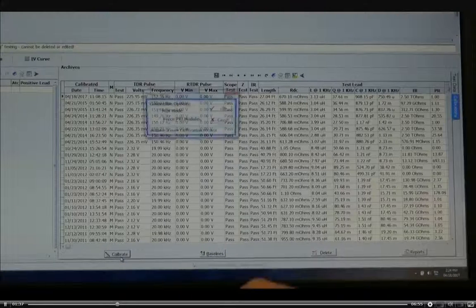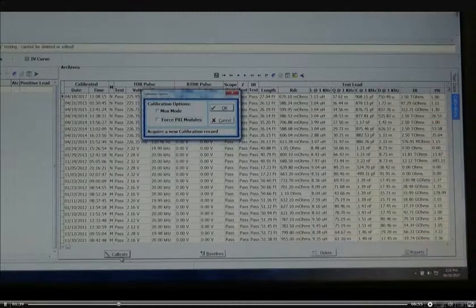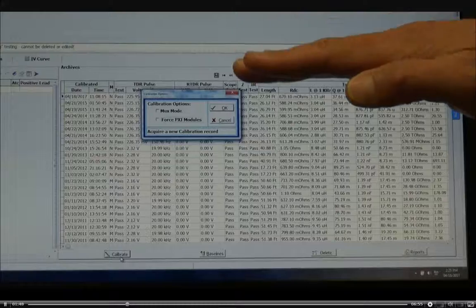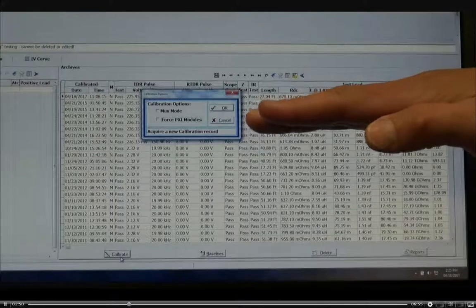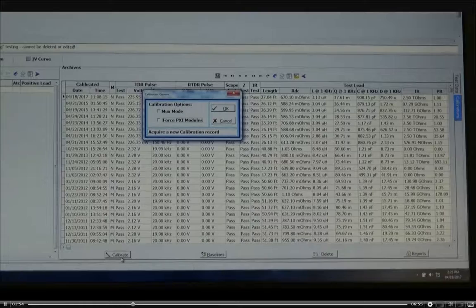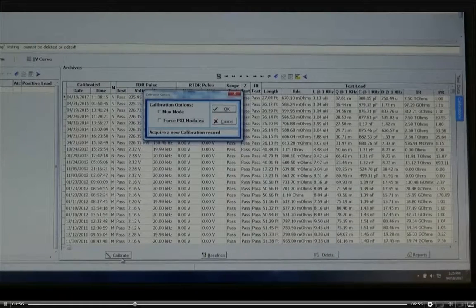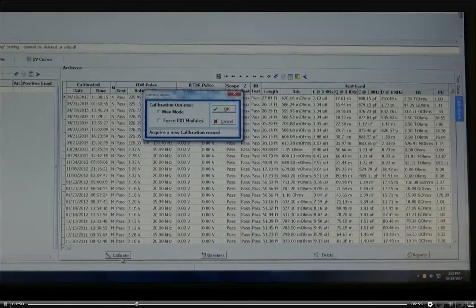So the way this works, the CHAR system is looking for a calibration once per day. Once you get the calibration done, it won't ask for it anymore. If you happen to just want to roll with the previous calibrations, you could actually do that as long as you're using the same test cables you've been doing, but the CHAR system is going to ask you to redo the calibration. It'll ask you 3 times. If you refuse it 3 times, it'll continue operating. But best thing to do is every time you start it up, give it a fresh calibration.